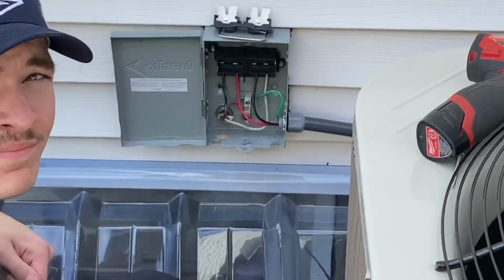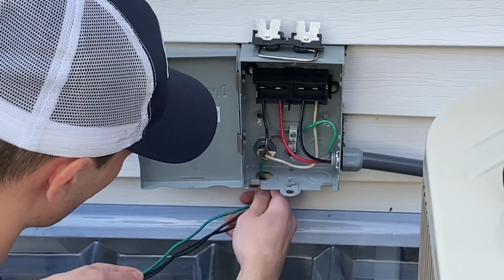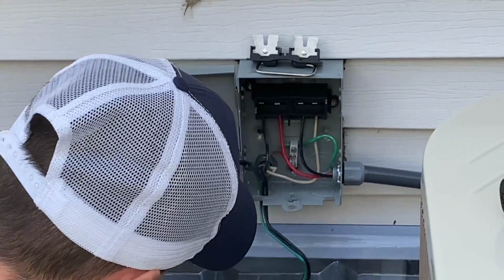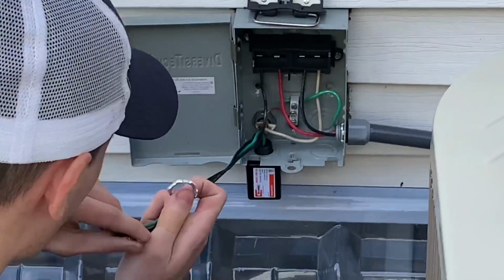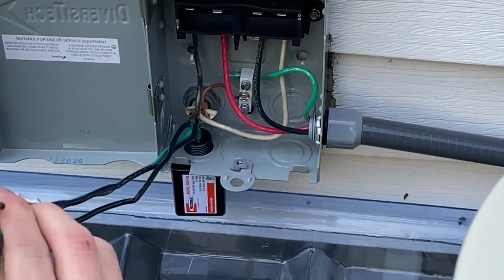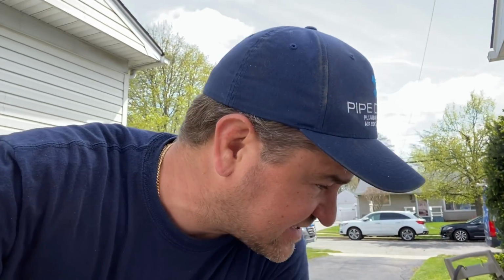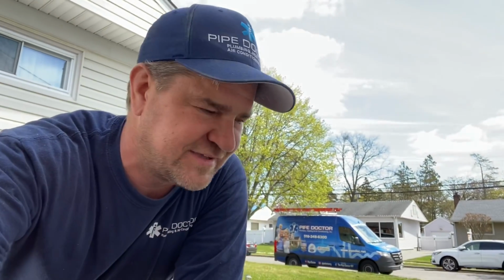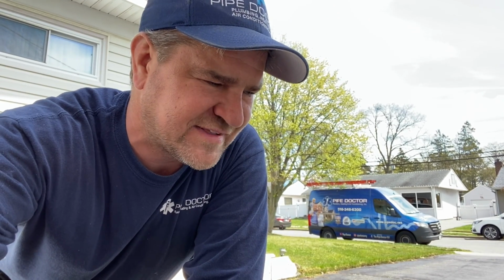We're going to wire that in, it gets wired in parallel to the line voltage on this machine, and we'll be protecting the outdoor condenser. Now if we had a sensitive air handler, for example with a control board like the Bosch, it'd also be a great idea to put one on that piece of equipment as well. However, when you factor in two surge protection devices for two pieces of equipment, it may be more beneficial and cost effective to have a licensed electrician install one on the main circuit breaker panel coming into the house. That way you have whole house protection. Just food for thought, guys.